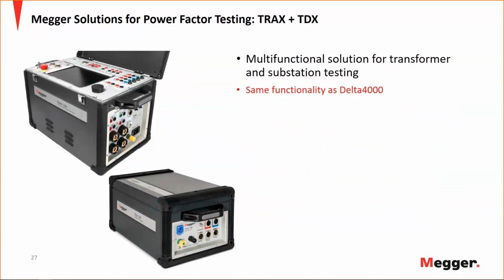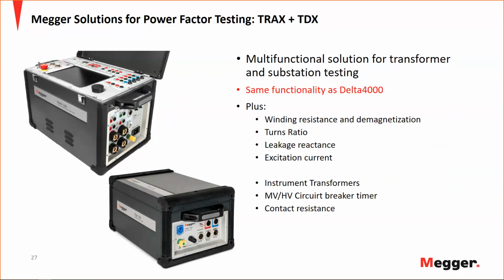Next, there is the Trax plus TDX. This is the multi-function solution for transformer and substation testing. This gives you the same functionality as the Delta, but adds in winding resistance and demag, turns ratio, leakage reactance, excitation current, and then further gives you the ability to test instrument transformers, circuit breakers, and contact resistance.